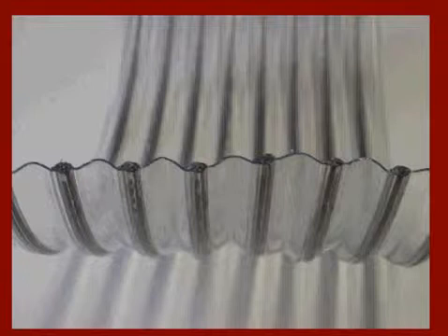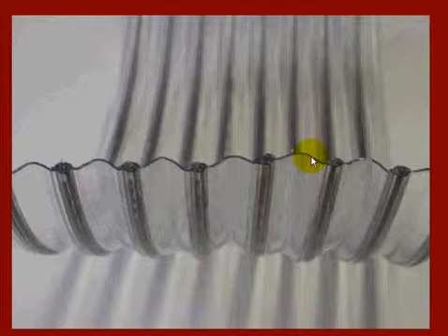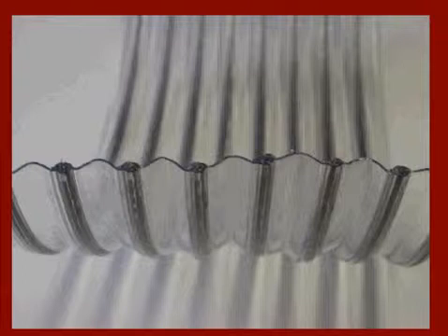That's the problem with flexible duct. This irregular surface, this corrugation, is the problem with flexible duct. And the more tightly compressed that flexible duct is, the worse it is. All right? Flexible duct should be installed fully extended. That means you pull it out as tightly as you can, which means that all your fittings that take off to the trunk duct, the ceiling box, whatever you're connecting it to, have to be nailed down, if you will, correctly. All right? You can't just come off the top of an 8x8 to 8 inch ceiling box.